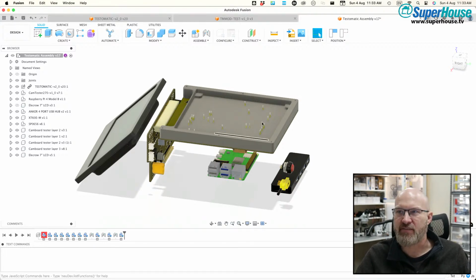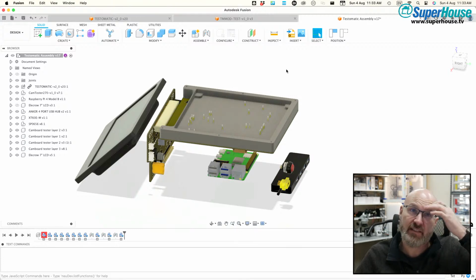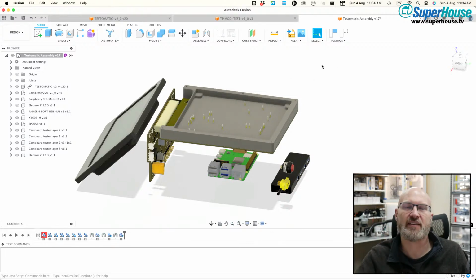That is one of the things I'm going to get this tester to do for me. I'm going to have it provide the 2.5 volt reference voltage coming up on one of these test pins, going to the input on the motor driver, and then it's going to tell the system to run its calibration. It'll load the firmware and then tell it to calibrate against that reference voltage and store it in EEPROM.